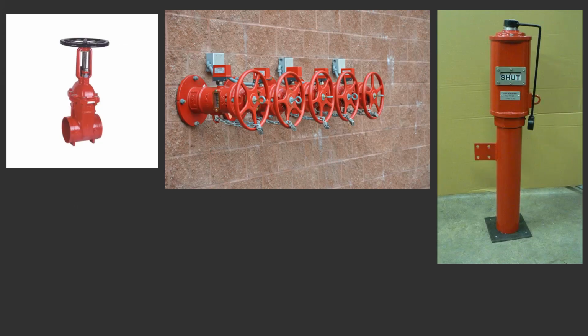For example, this one up here on our left is the outside stem and yoke. This one sitting here I can tell is closed, because when these are opened, this threaded rod goes through this body and is connected to the actual valve. Water would be coming through here. Right now it's closed. It stops. Nothing over here. If you open it, the little gate rises and then water can get through. When you open it, this threaded rod comes up the top of the wheel. There's a little nub right there, and it'll stick out however far it has to for the valve to be fully open. So there'll be threaded rod sticking up past the edge of the picture potentially, depending on how big the valve is.